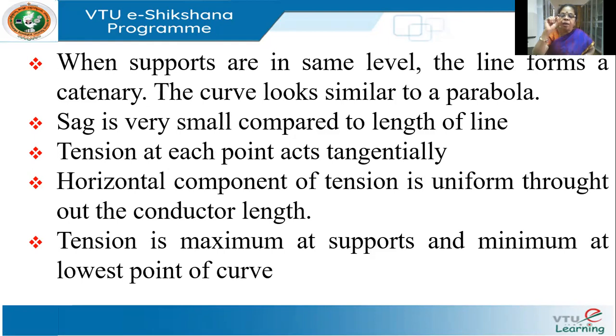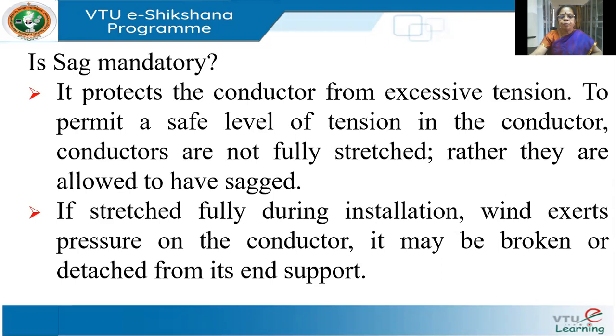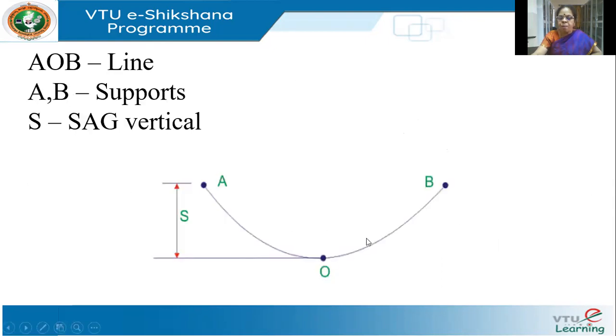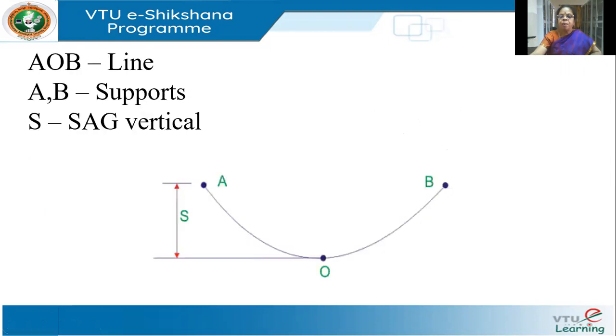At every point along the conductor, the tension acts tangentially to the conductor. The horizontal component of tension is uniform throughout the length of the conductor — throughout AOB it is uniform. The tension is maximum at the supports A and B and minimum at the lowest point O.